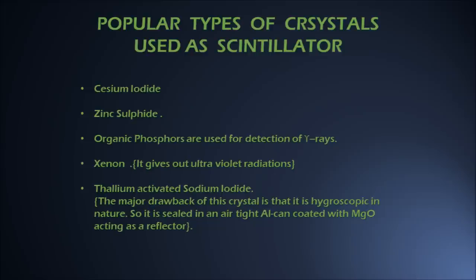The most popular crystal used as a scintillator is thallium-activated sodium iodide, because it has more efficiency in comparison to other crystals used for this purpose. However, the major drawback of this crystal is that it is hygroscopic in nature — that is, it can get spoiled due to moisture. Due to this reason, this crystal is sealed in an air-tight aluminum can which is coated with magnesium oxide acting as a reflector.